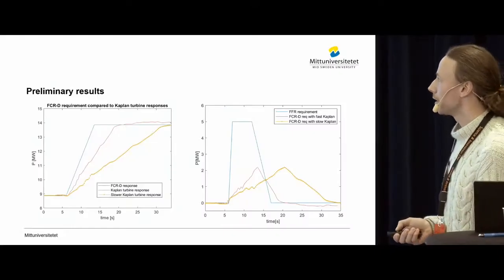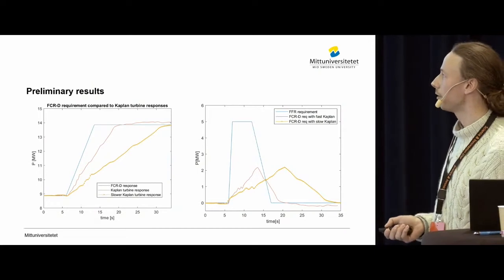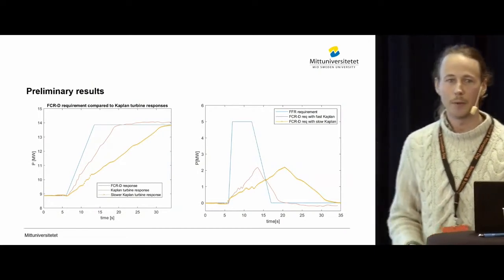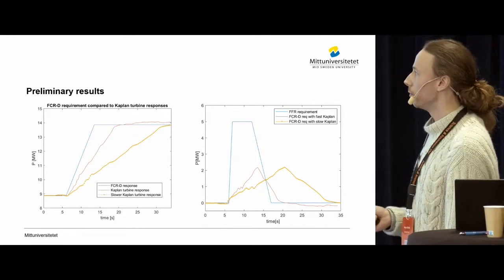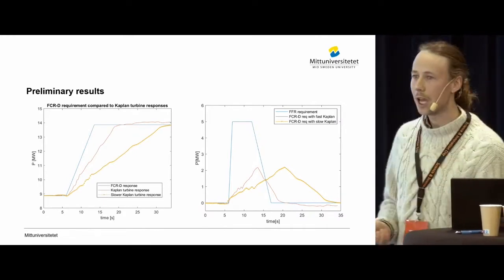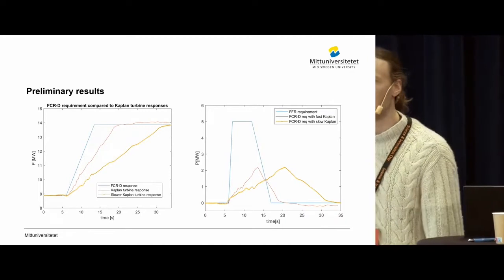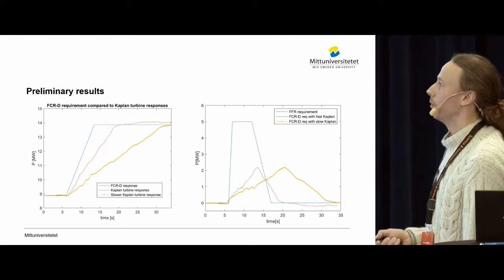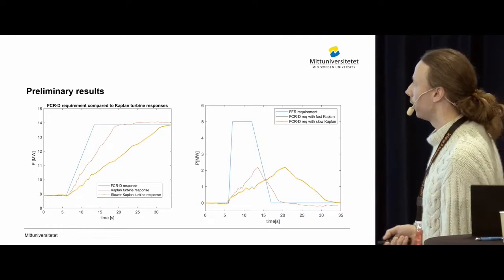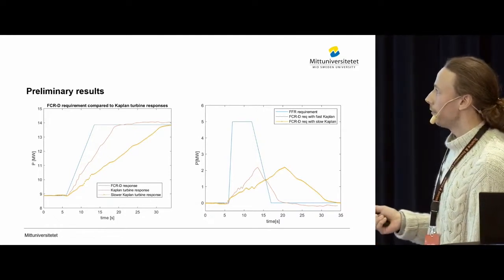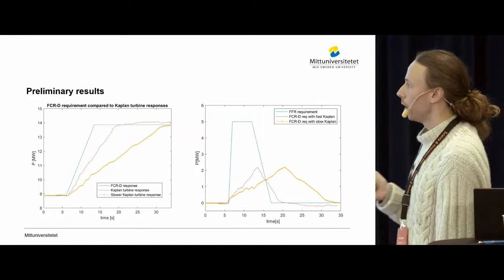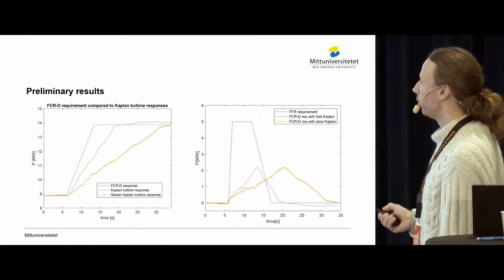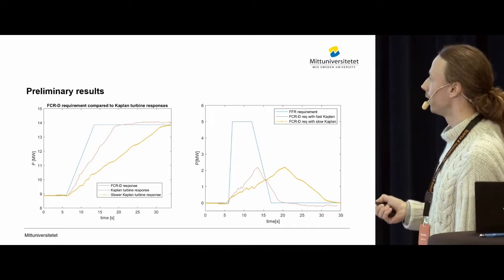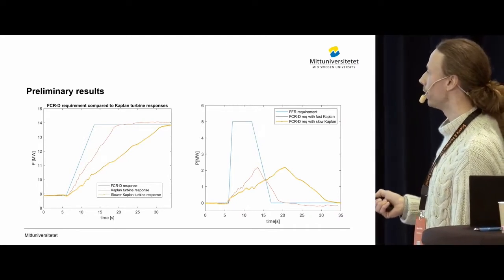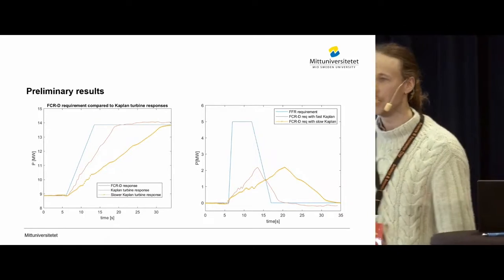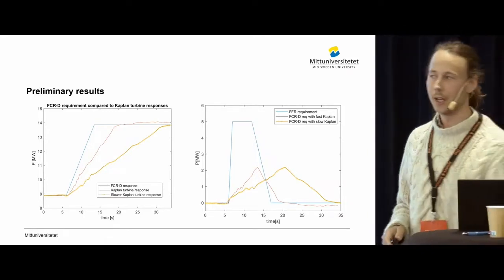I'd like to present some preliminary results. In this left graph, I plotted the requirements to provide FCRD - that's this blue line. And here are some Kaplan turbine responses - how fast do they react? I have one fast Kaplan turbine and one slower Kaplan turbine. I've taken the difference between the blue and red, and the blue and yellow, and plotted this in the right-hand graph. The integral of these graphs is the energy needed for the system to provide FCRD.